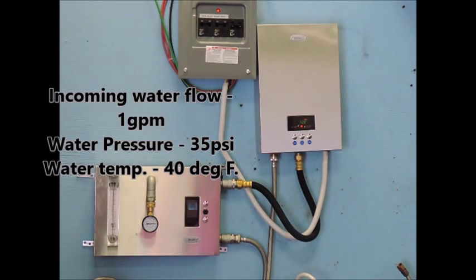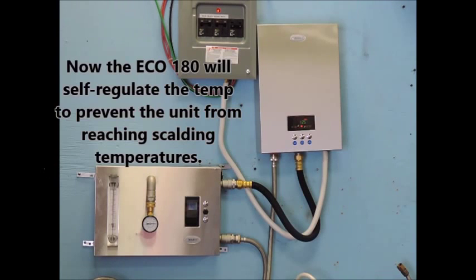Now, bringing the water flow down to a gallon per minute, still with 35 psi and a water temp of 40 degrees Fahrenheit, we are hitting the max set point of 125 degrees.